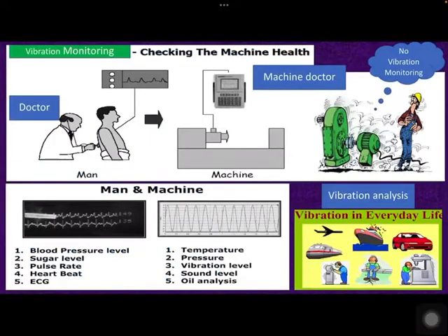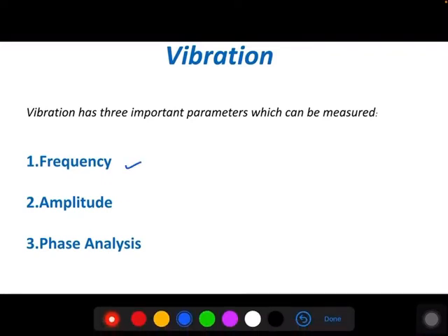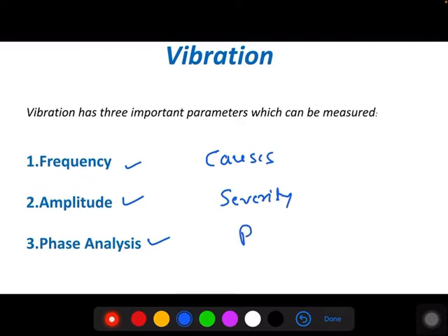Hi friends, welcome to Mega Technical Hub. In the last sessions we discussed two important parameters: frequency and amplitude. Frequency tells us about the probable causes of a machinery problem, and amplitude tells us about the severity. Today we are going to discuss the third important parameter, that is phase analysis, which is mainly used in vibration to pinpoint machinery defects.